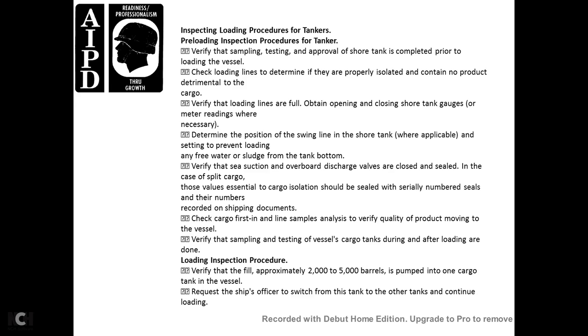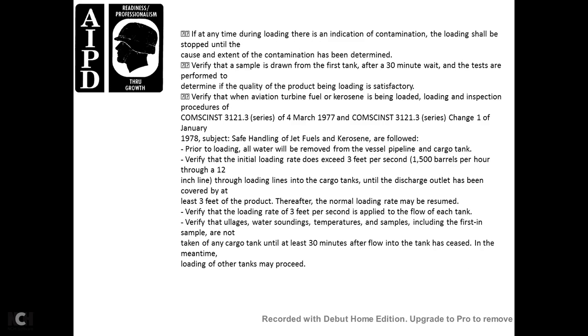If at any time during loading contamination is indicated, loading should be stopped until the cause and extent of contamination are determined. Verify samples drawn from the first tank are allowed to settle for 30 minutes and tests performed to determine product quality before loading continues.